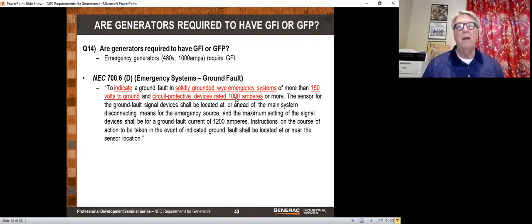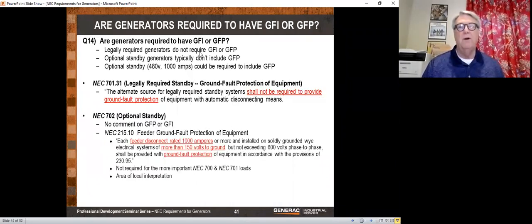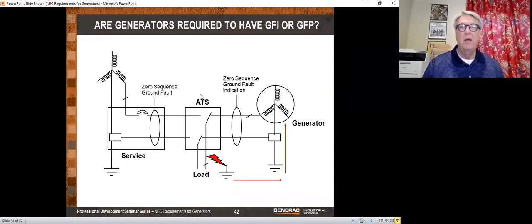So most of our generators are not going to have ground fault indication. And remember, we never put ground fault protection. We never trip the generator. We just put ground fault indication. And this gives you some more information on that. You can see that legally required does not require ground fault indication, and optional standby doesn't. For legally required, there is an exception there, but I won't get into that.